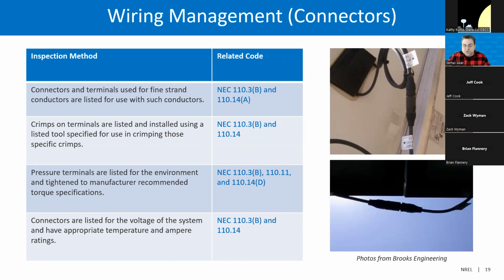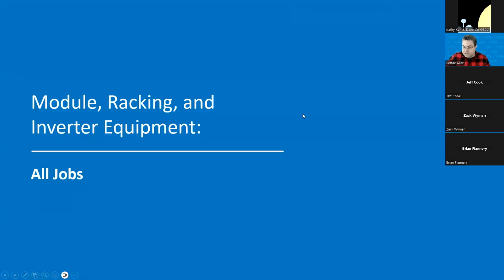Connectors and terminals used for fine strand conductors must be listed for use with such conductors. Crimp-on terminals must be listed and installed using listed tools specified for crimping those specific crimps. Pressure terminals must be listed for the environment and tightened to the manufacturer's recommended torque specification. And the connectors must be listed for the voltage of the system and have appropriate temperature and ampere ratings. So this is basically covering the wiring management.